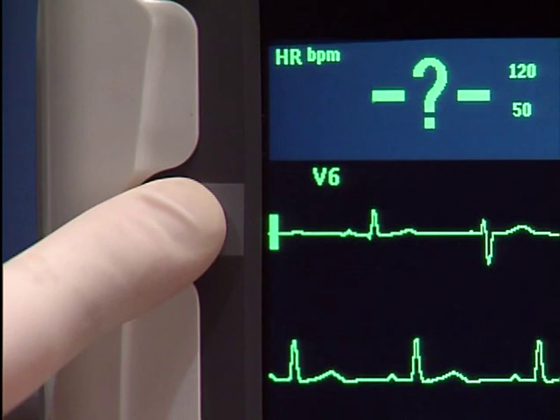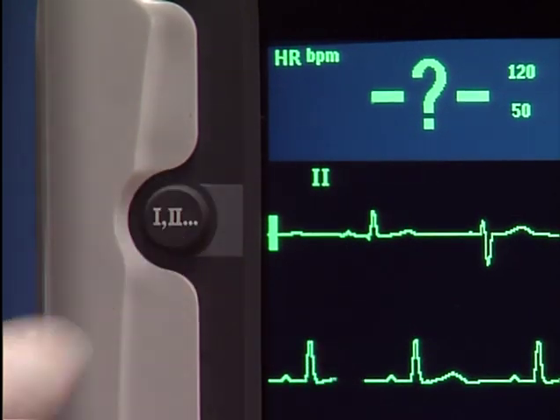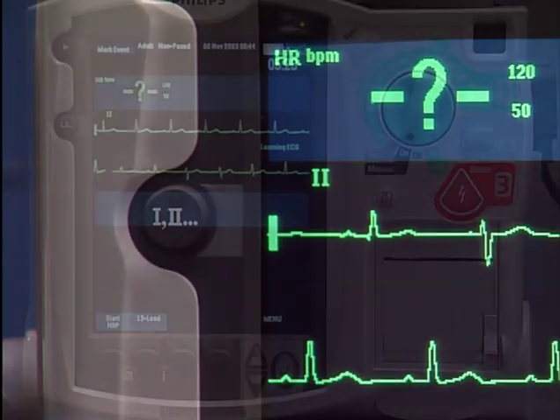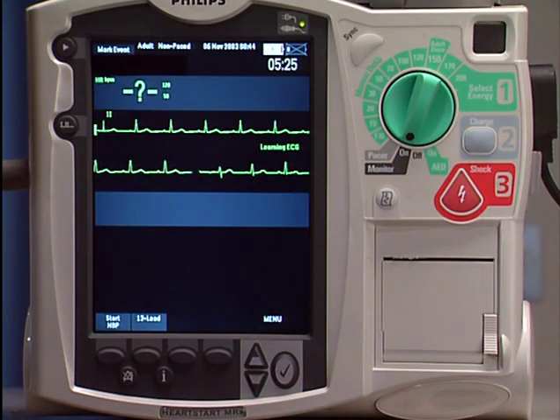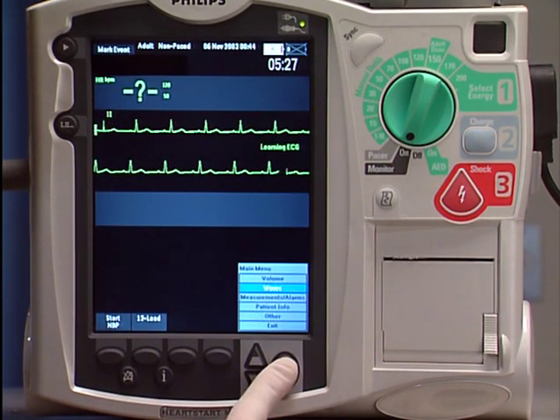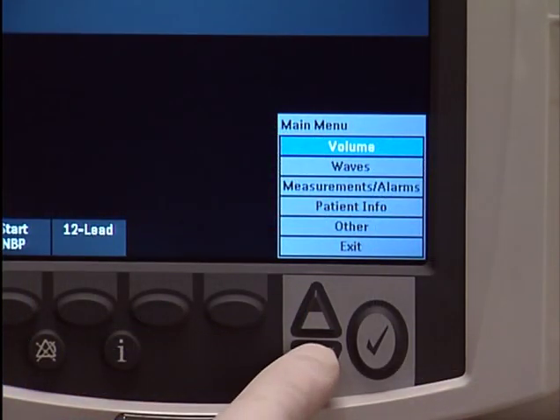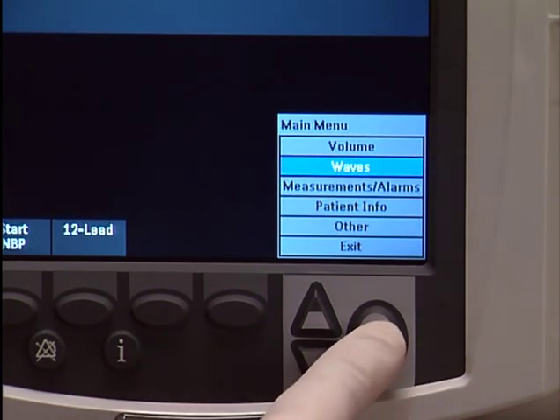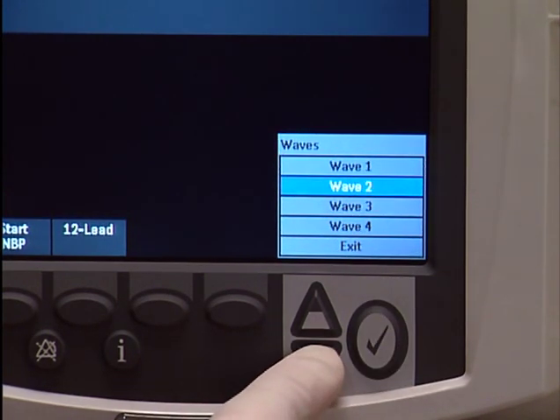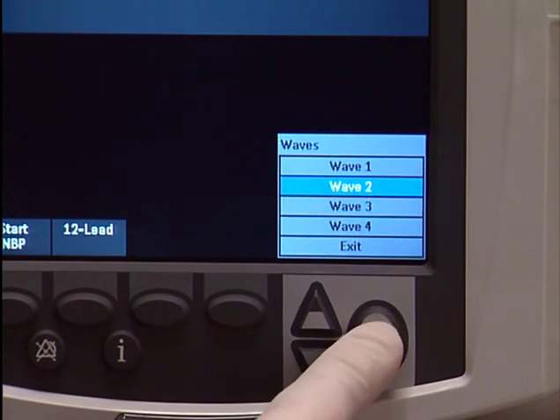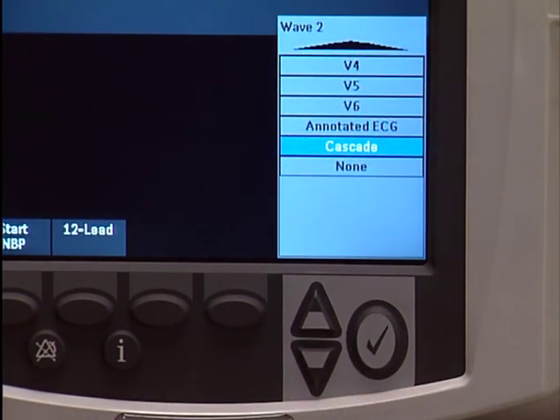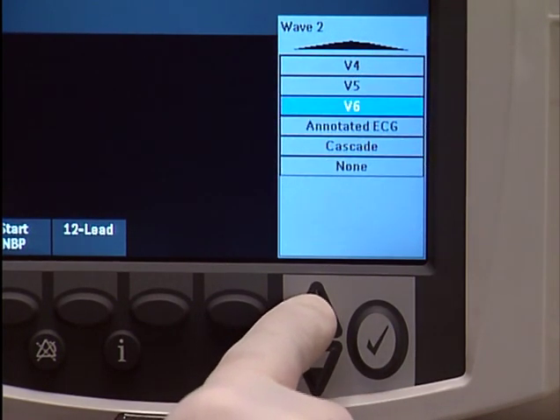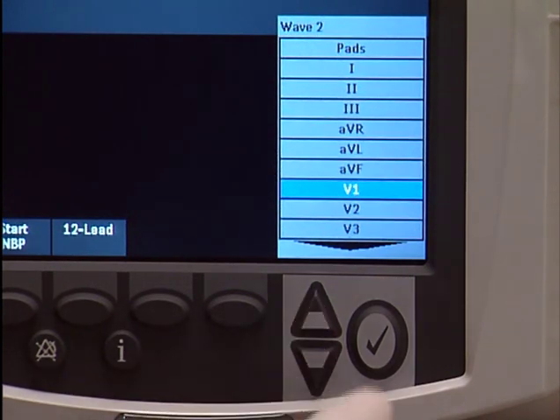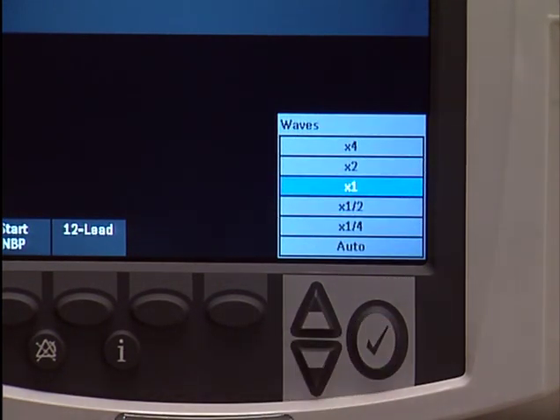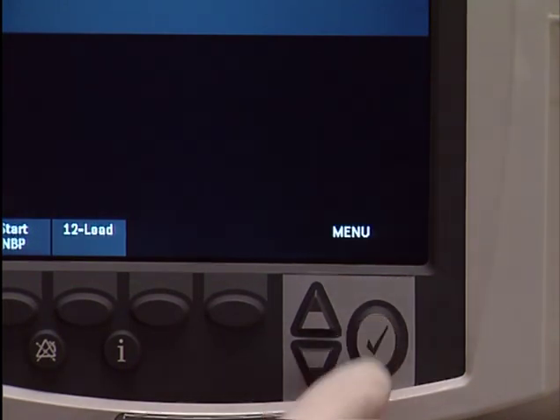Press the Lead Select button to display the desired lead in wave sector 1. To change the waveform displayed in wave sector 2, 3, or 4, press the Menu Select button. Navigate to Waves. Select the desired wave and press Menu Select again. Select the desired lead. And finally choose the preferred wave size and press Menu Select again.